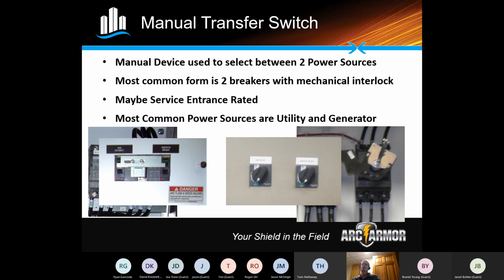Sorry about that. Here's what a typical manual transfer switch could look like. It's got two breakers here: your main breaker on the left, your emergency breaker on the right. The top side of the emergency breaker is going to the generator receptacle. There's a slider here that slides between the two breaker on-off switches, so that if it's slid to the right, the breaker on the left is not operable. If it's slid to the left, then the breaker on the right is not operable. So that's one way of doing that.